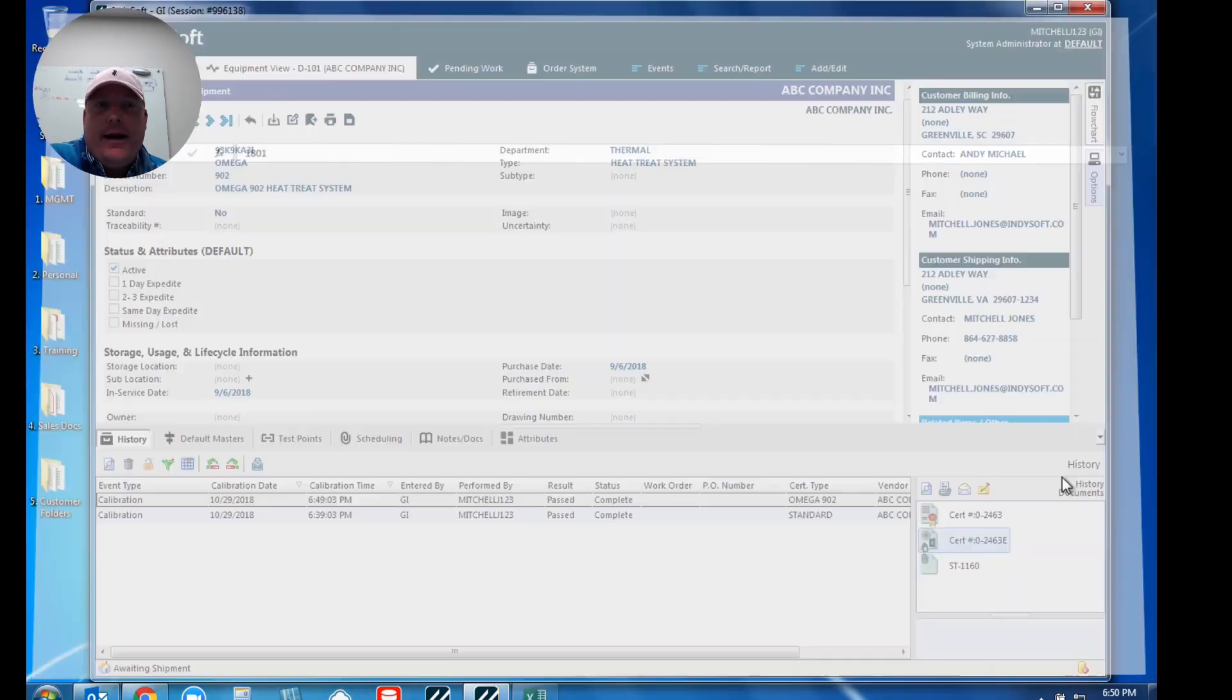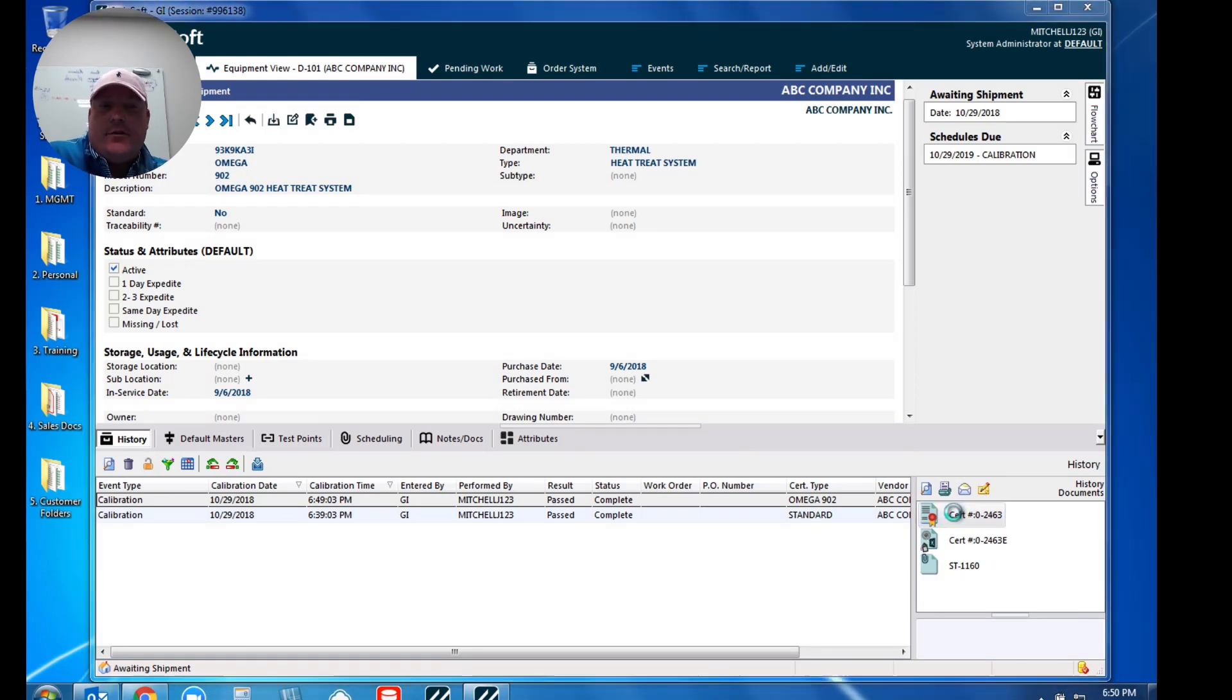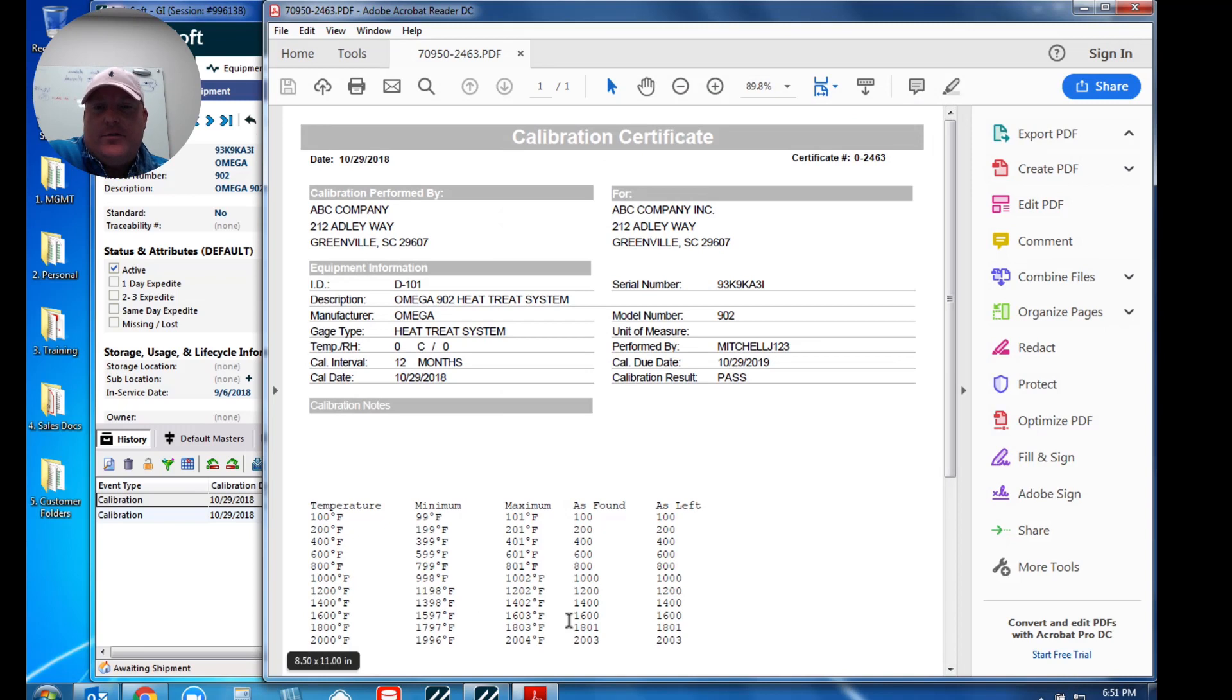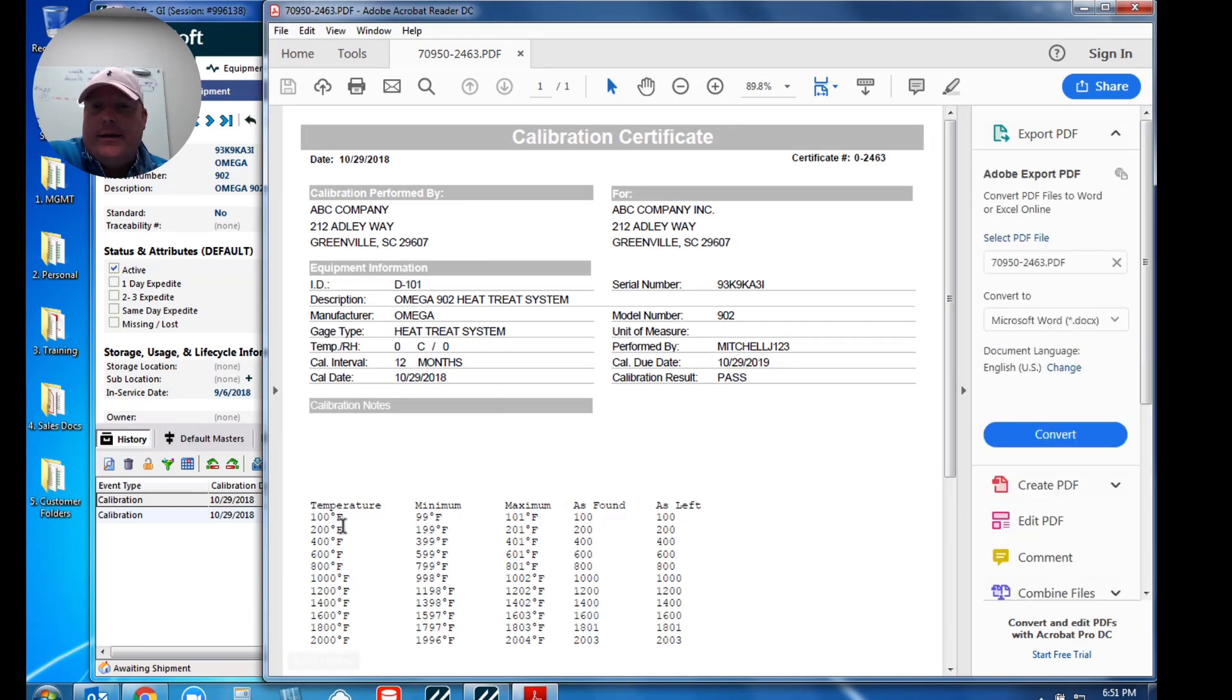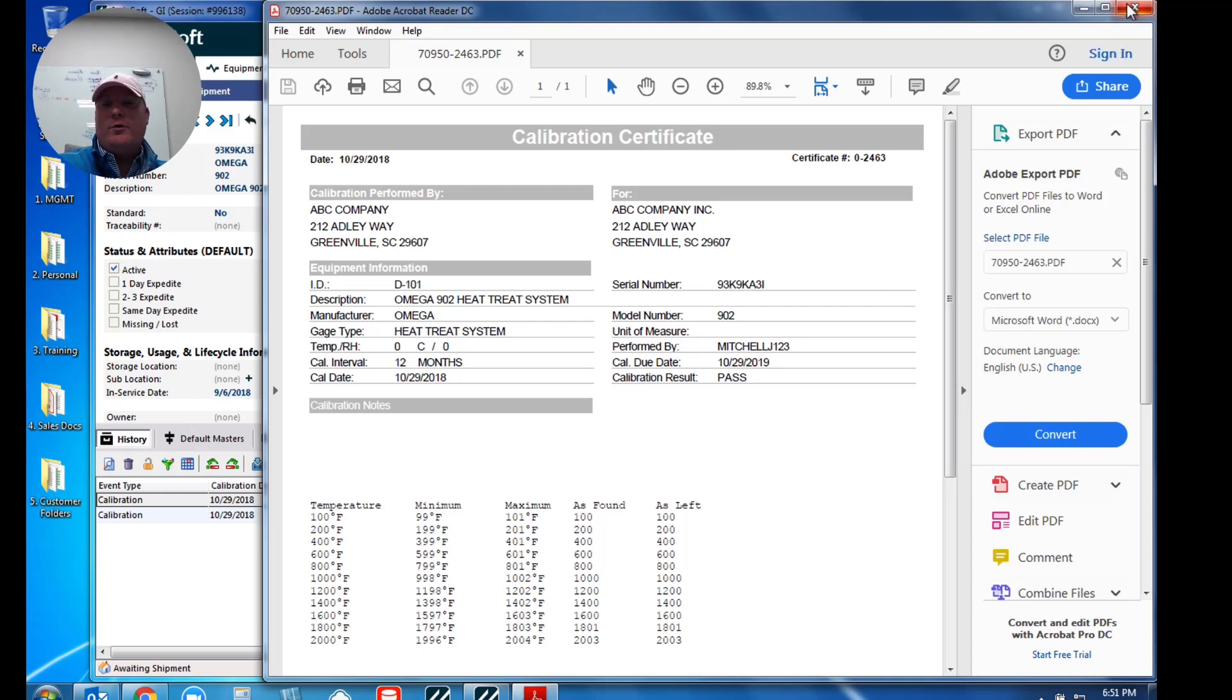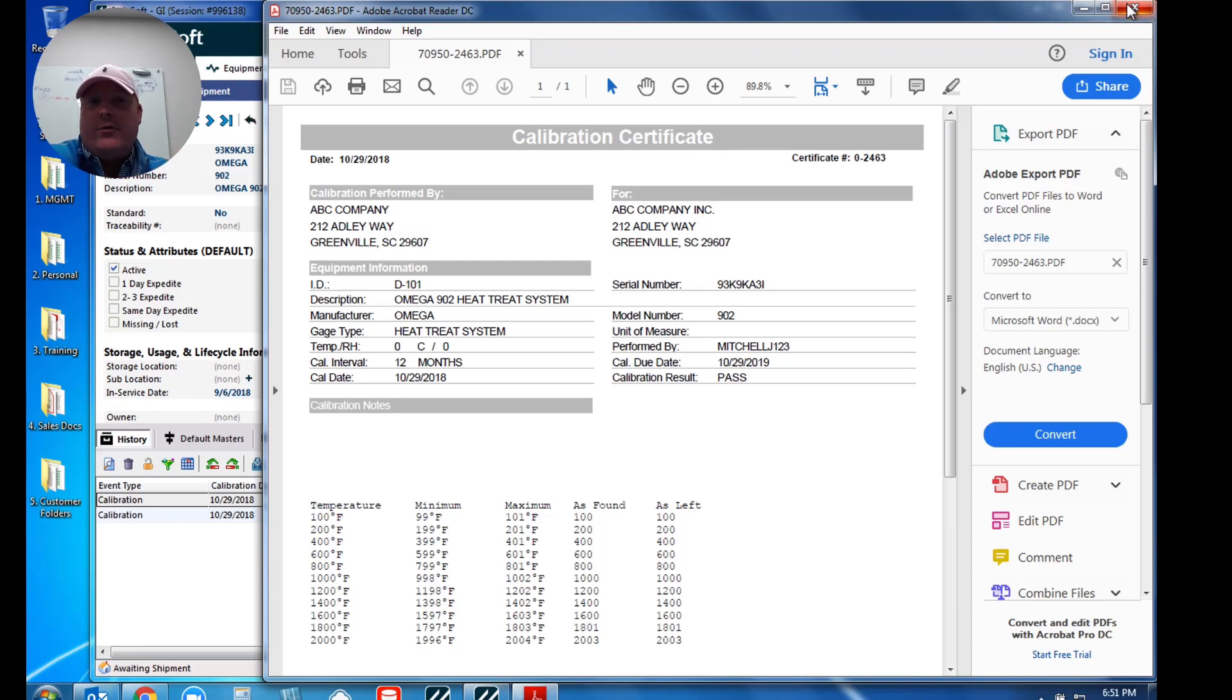But now if I go back and actually look at my PDF certificate that the software generates, when I open this up, you'll notice that section of those data points was actually embedded in. So you'll see my temperature, my min, my max, my as found, and my as left. So essentially what we're doing is we're taking a certain section of that Excel file and we're embedding that within to your PDF document for you.